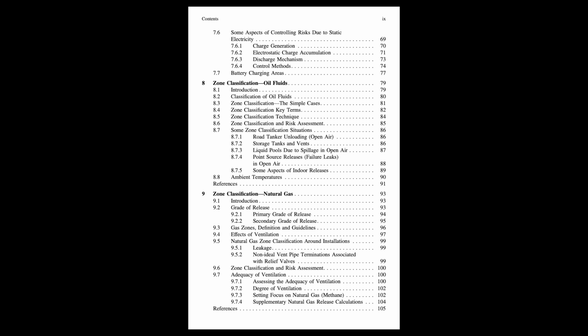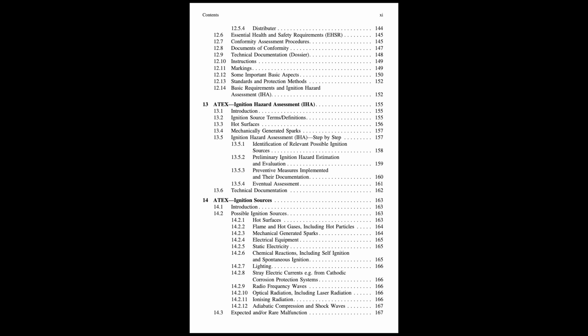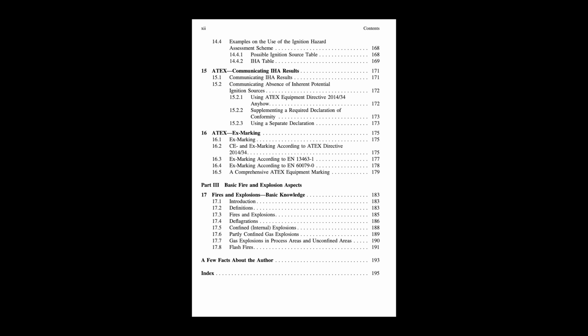Okay, finally the guide wraps up by touching on the science of fires and explosions themselves. What are the key distinctions here? It clarifies the difference. A fire is combustion, but an explosion involves a very rapid expansion of volume, usually generating a pressure wave. We're mostly concerned with premixed fuel-air explosions. And the most common type? Is a deflagration. That's where the flame front travels through the unburnt mixture at subsonic speed, faster than a normal fire, but slower than the speed of sound. This is what causes the pressure rise in vessels or buildings.